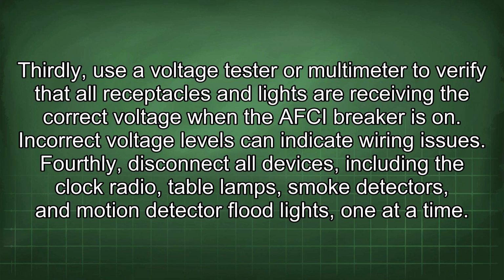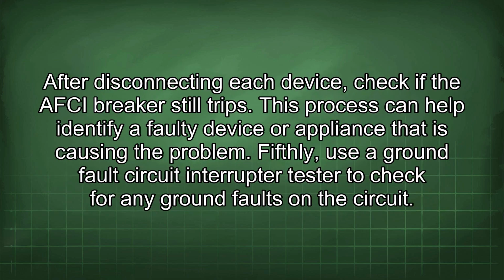Fourthly, disconnect all devices, including the clock radio, table lamps, smoke detectors, and motion detector floodlights, one at a time. After disconnecting each device, check if the AFCI breaker still trips. This process can help identify a faulty device or appliance that is causing the problem.